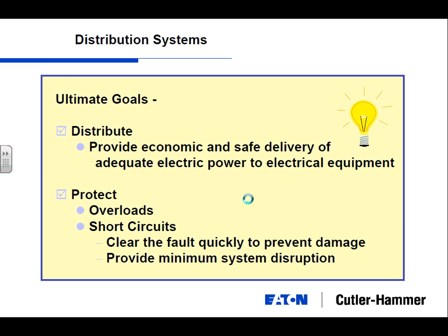And if I go out to that transformer that exploded on Monday night, and say I had to go in and work on that transformer hot or something while it was still active, I would have to wear, basically it'd be looking like you'd be wearing like a nuclear suit to go in there to try and protect yourself. And these are dictated by the NEC code. They look at arc flash energy, and once you calculate that, you determine how much protection you need to work on that equipment.